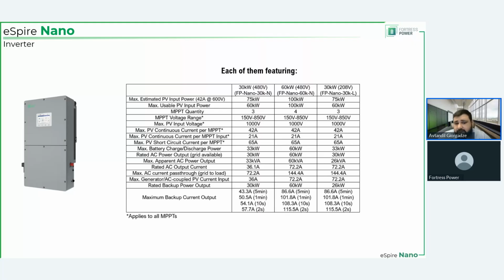But AC side capabilities are not only influenced by current, but also by voltage, because both of them are considered when determining power for the AC. So because you have 208, you multiply by 208 and the square root of 3, and that's how you get 26. And if you multiply 72.2 by 480 volts and then the square root of 3, that's when you get 60 kilowatts.